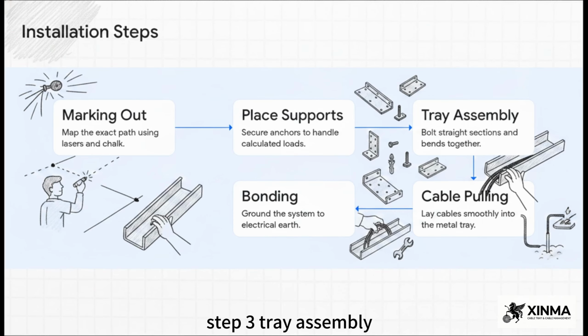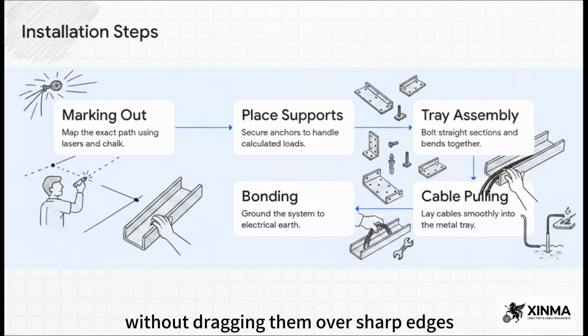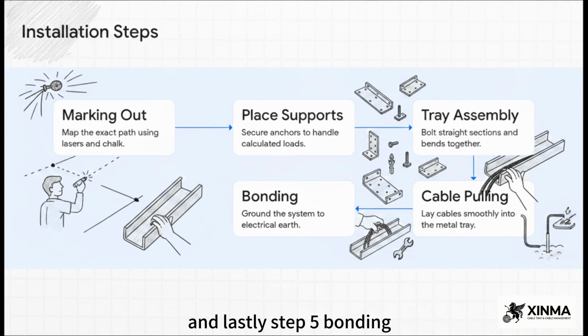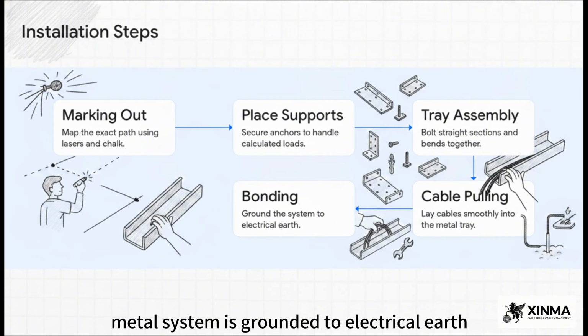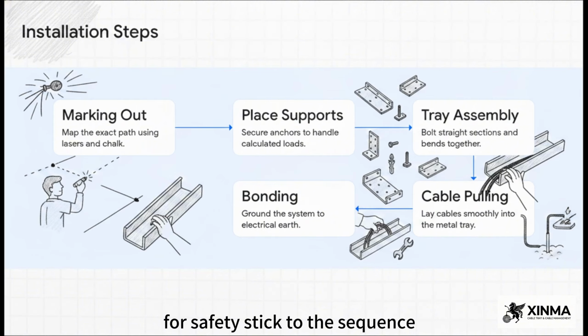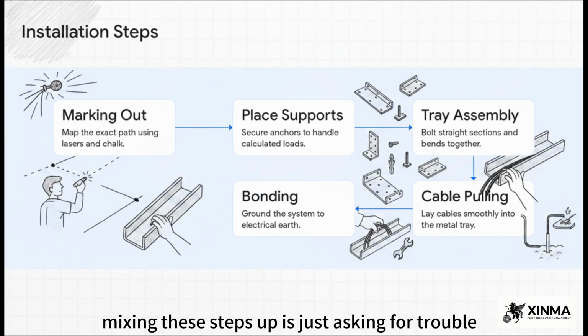Step 3. Tray assembly. Bolting the straight sections, bends, and tees onto the brackets. Step 4. Cable pulling. The electricians come in, laying cables smoothly without dragging them over sharp edges. And lastly, Step 5. Bonding. You have to ensure the entire continuous metal system is grounded to electrical earth for safety. Stick to the sequence. Mixing these steps up is just asking for trouble.